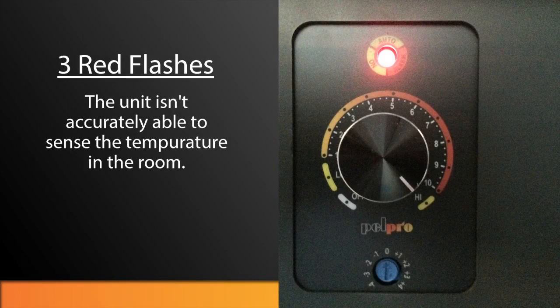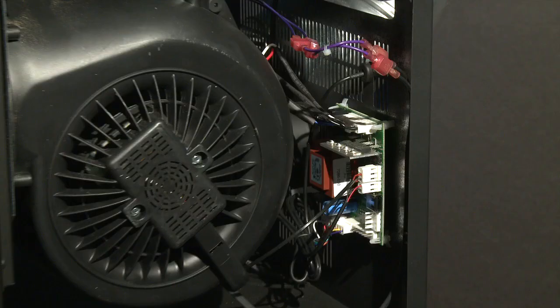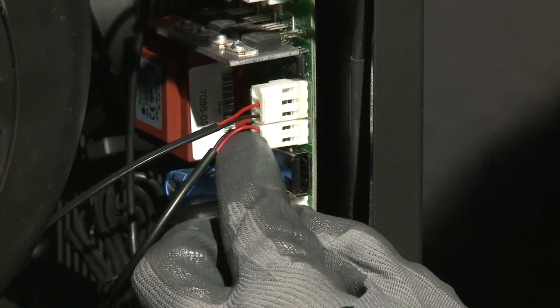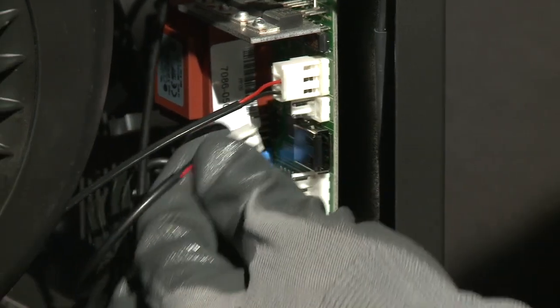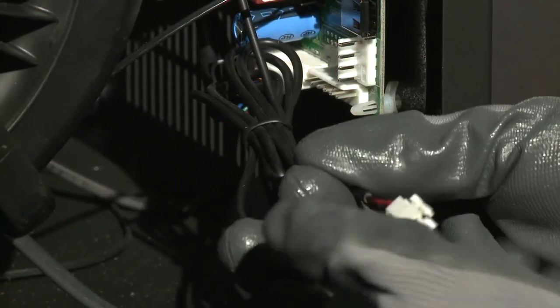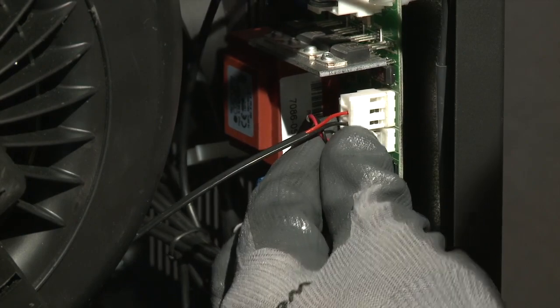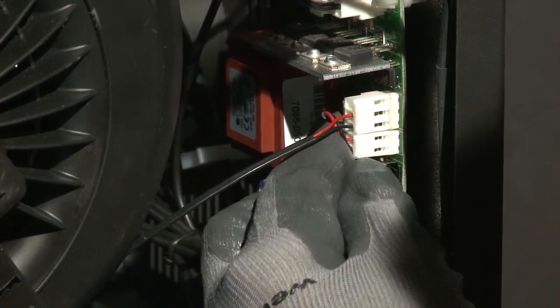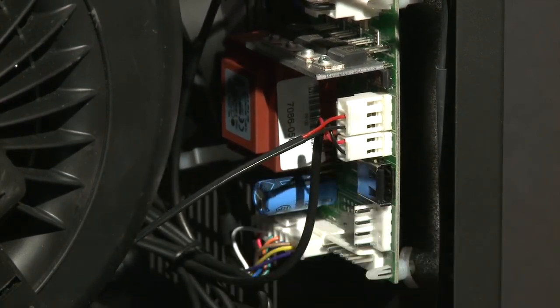3 red flashes means that the unit isn't accurately able to sense the temperature in the room. This could mean that the ambient temperature probe has been disconnected from the board. Simply plug the probe back into the board. If this does not work, unplug the probe, inspect the connection, and check the entire wire for damage. Plug the probe back in. If you still see 3 red flashes on the control, replace the ambient temperature probe with a new one.